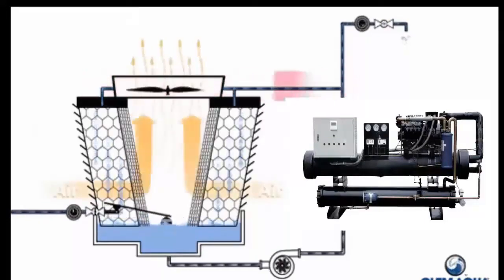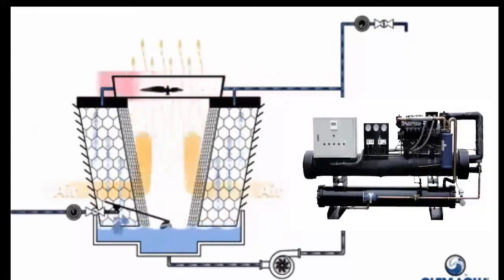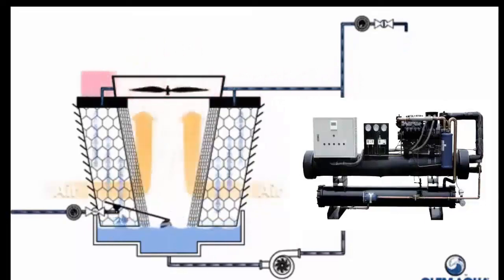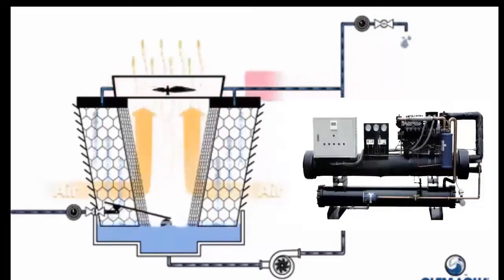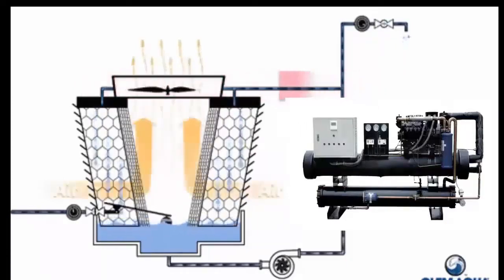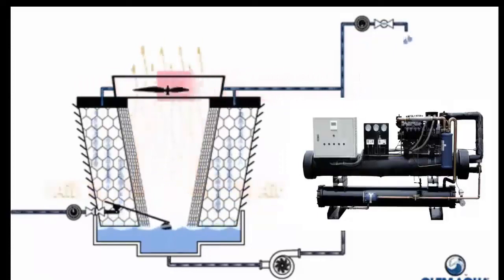This means that despite both water and air being in the environment, the water is going to have a lower temperature than the air — depending on the relative humidity, but a lower average temperature. This guarantees better heat exchange in the condenser, meaning we extract the heat more easily, giving us a more comfortable, calmer refrigeration circuit to remove the heat collected from the chilled water.